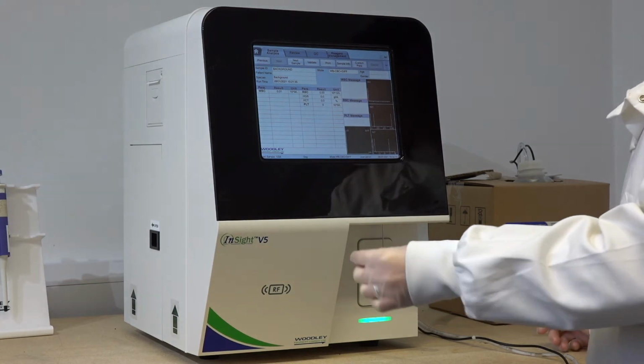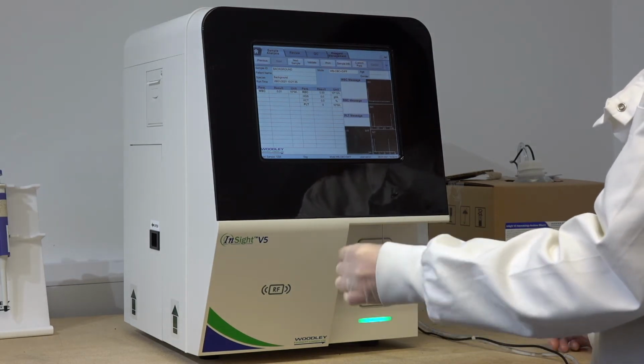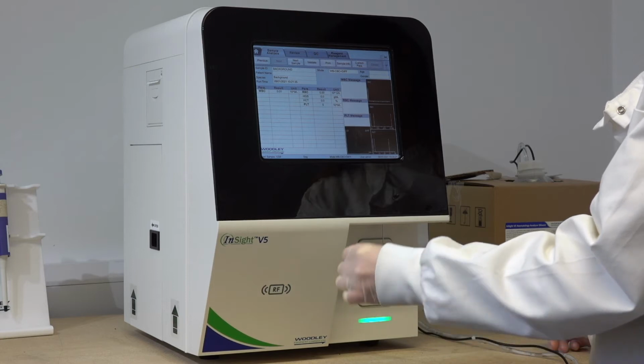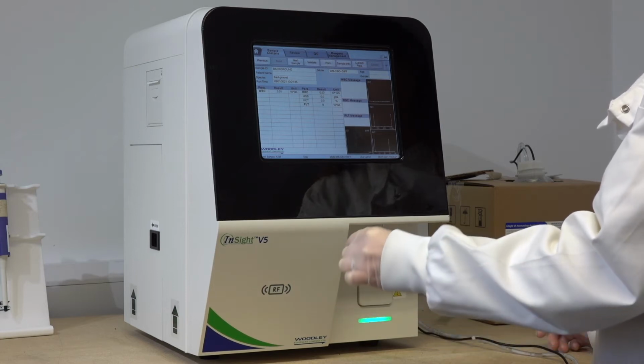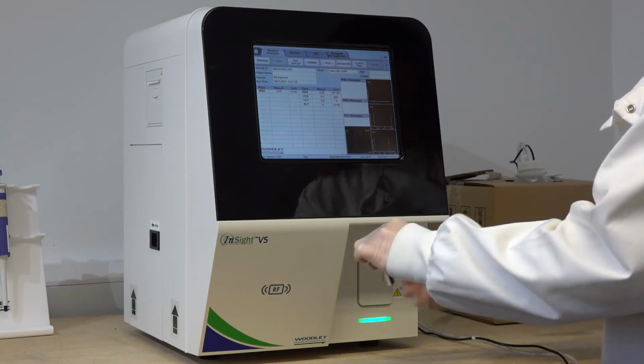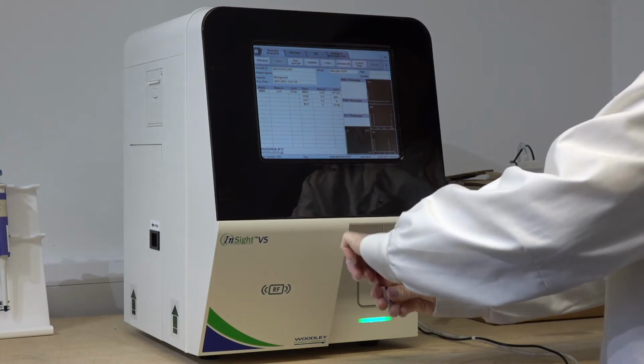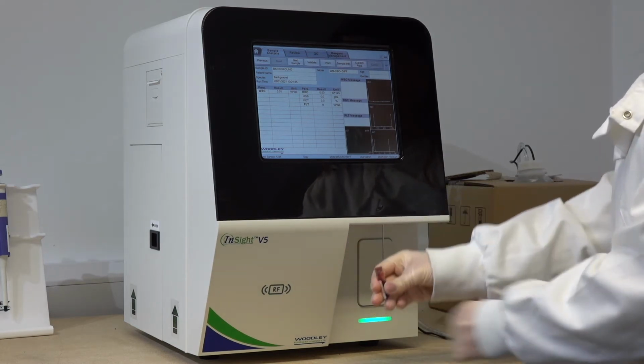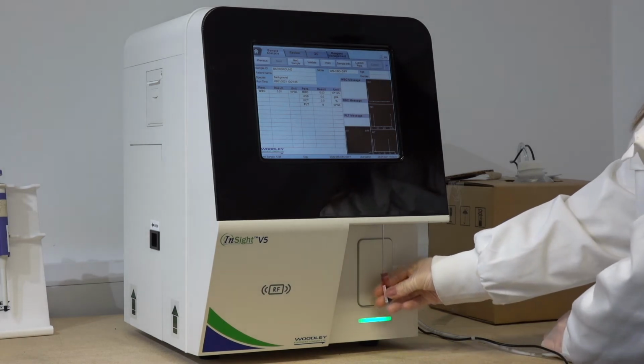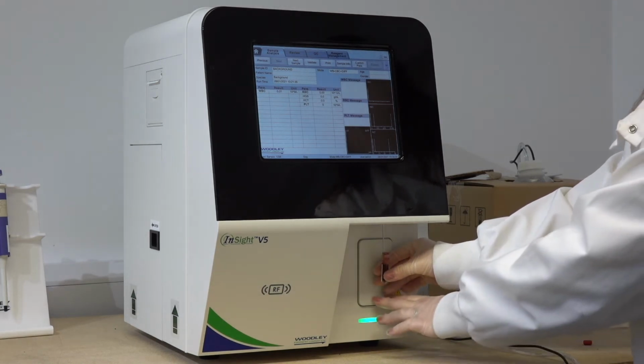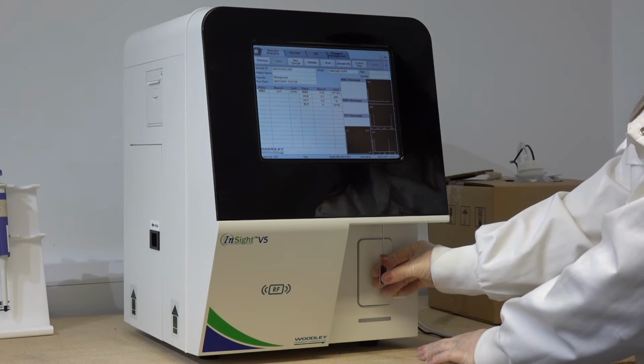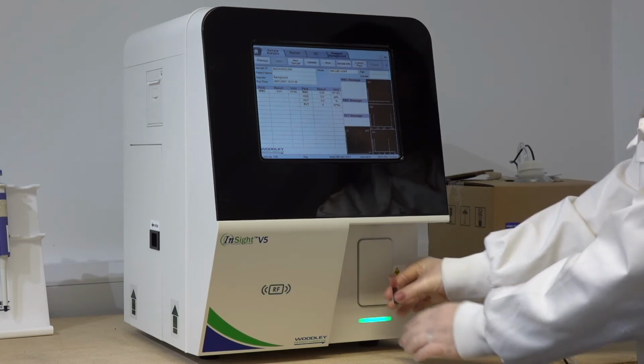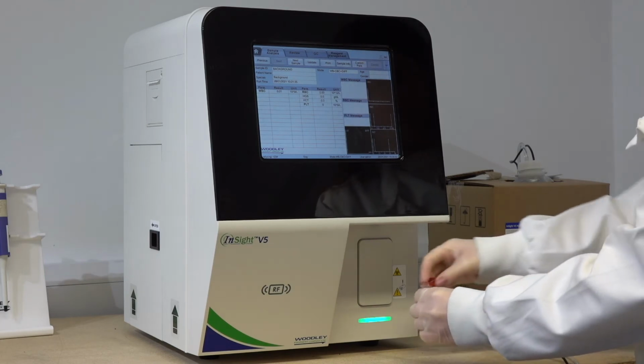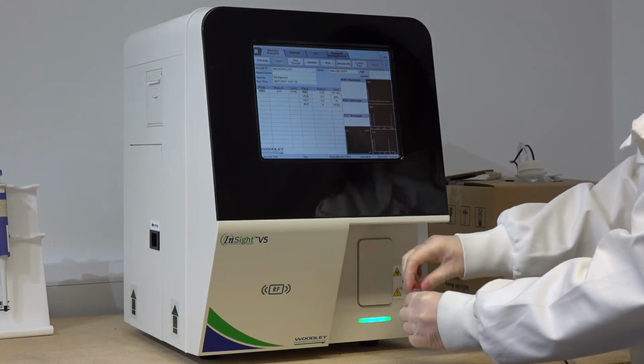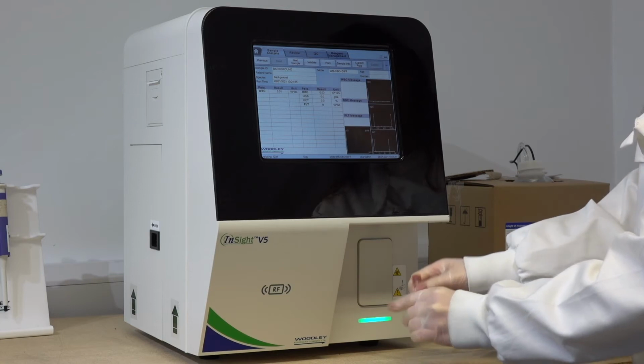Ensure the EDTA whole blood sample is at room temperature and gently mixed before analysis. Remove the sample lid and place the sample under the probe. Push the back plate to begin analysis. When the analyzer beeps, the sample can be removed from the sampling area. Place the lid back on the sample tube.